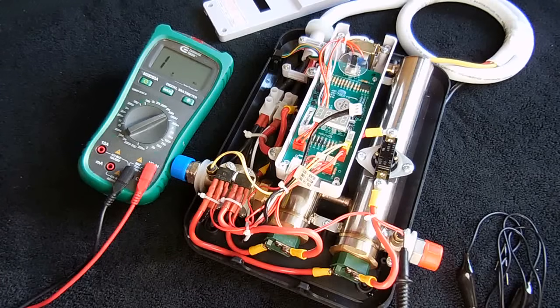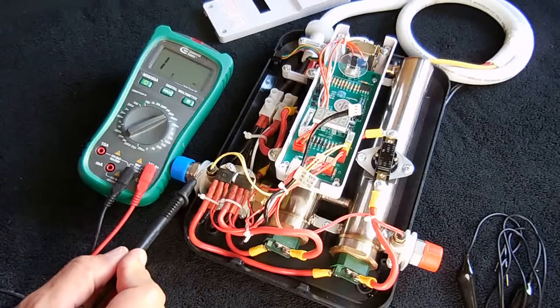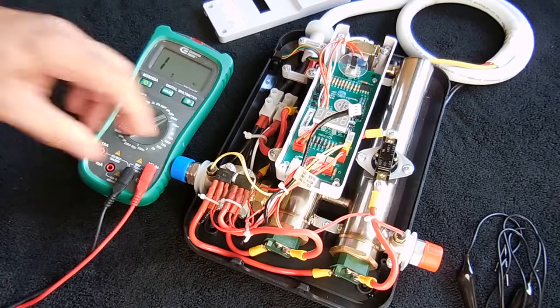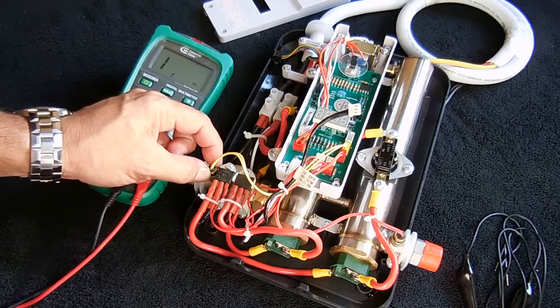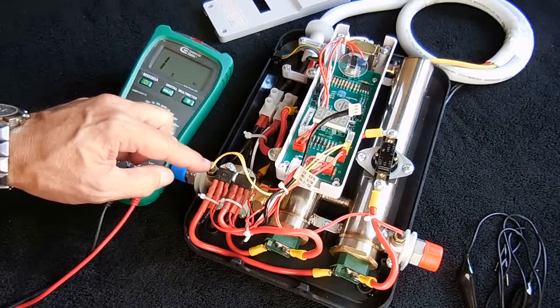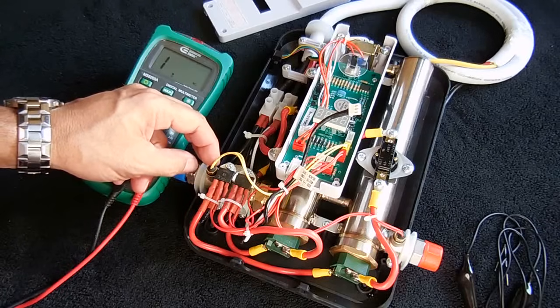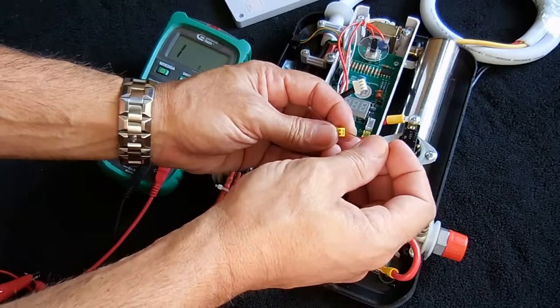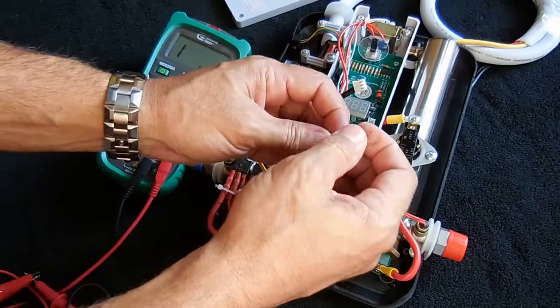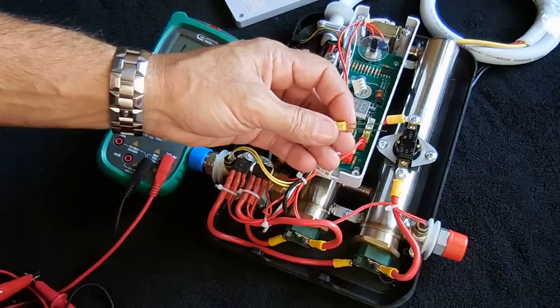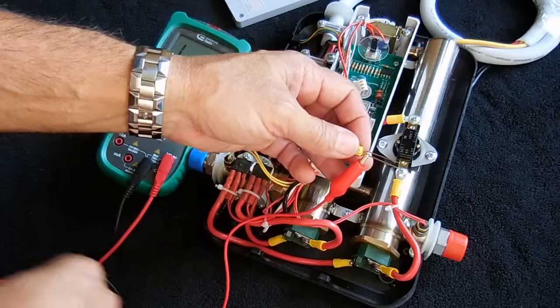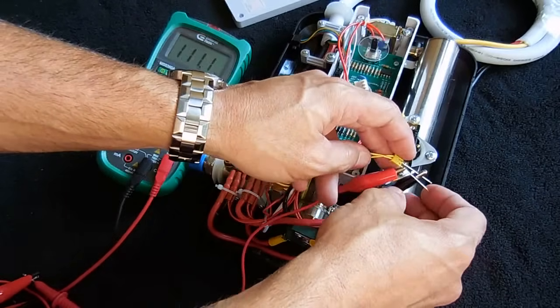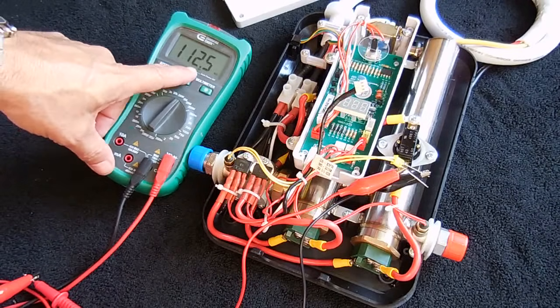On the other side here, you can see there's an outlet temperature sensor. The control board monitors the inlet temperature and the outlet temperature. Now these are called NTC thermistors, which means negative temperature coefficient. As the temperature of the thermistor gets cooler, the resistance goes higher. As the temperature of the thermistor inside the sensor gets higher, the resistance goes lower. I'm going to give you a quick demo. Just unplug one right here, take the connector, insert a needle. Take another one there, connect one jumper wire there and connect your other jumper wire there, making sure nothing's shorted.